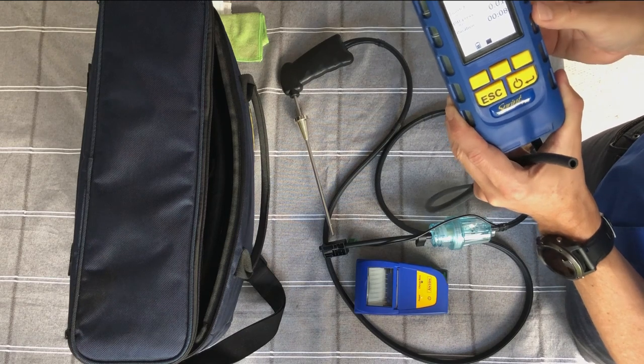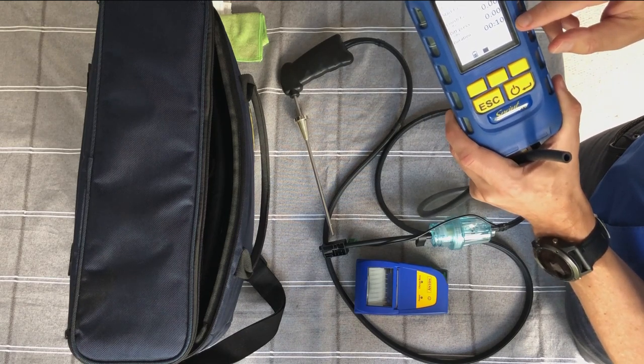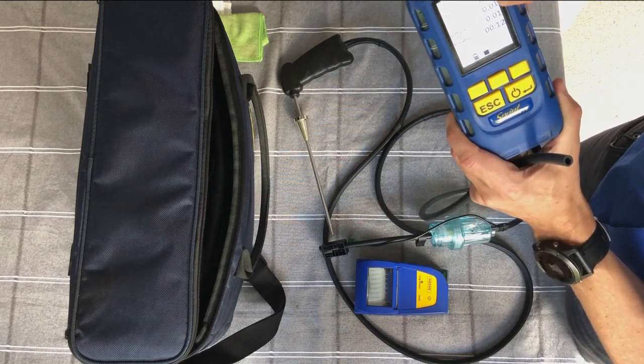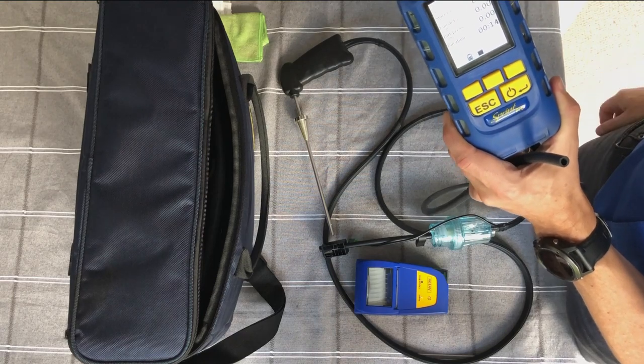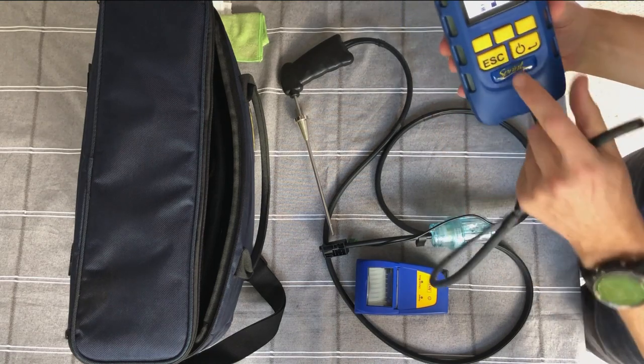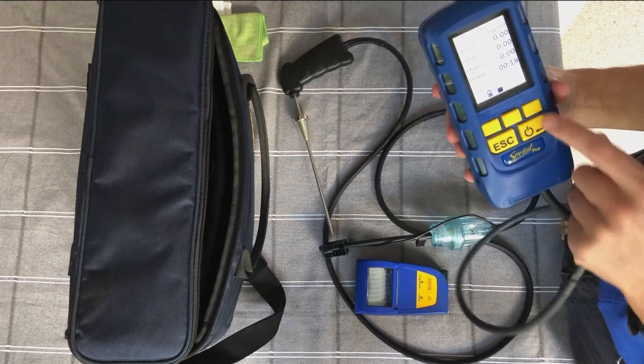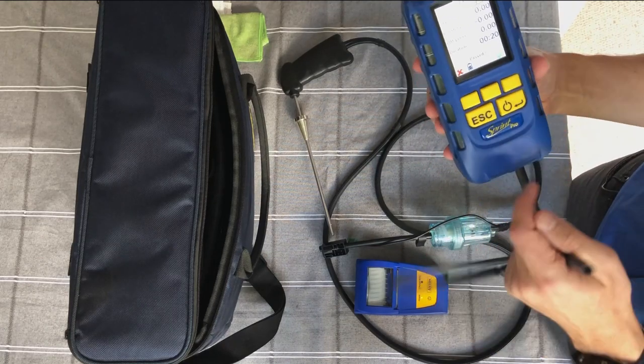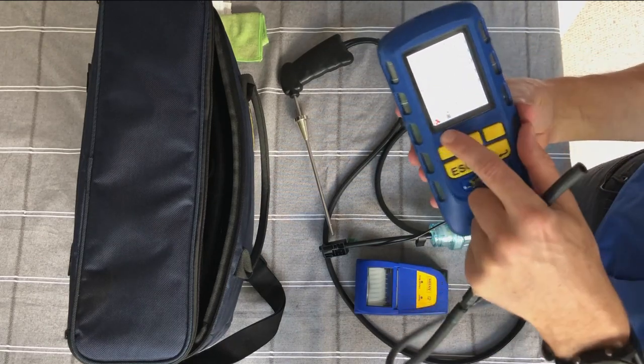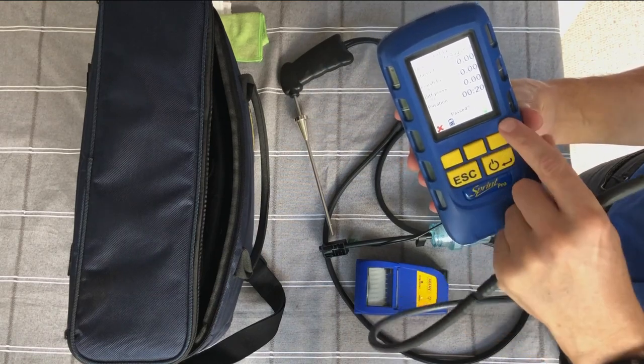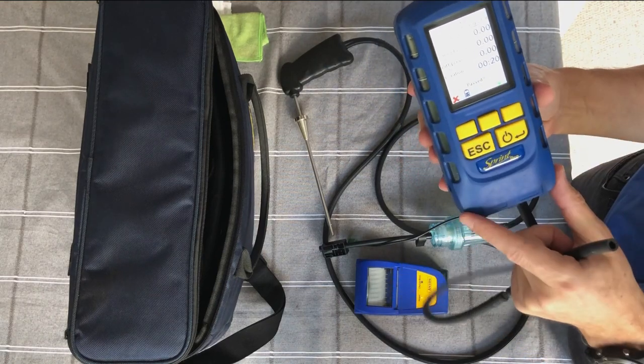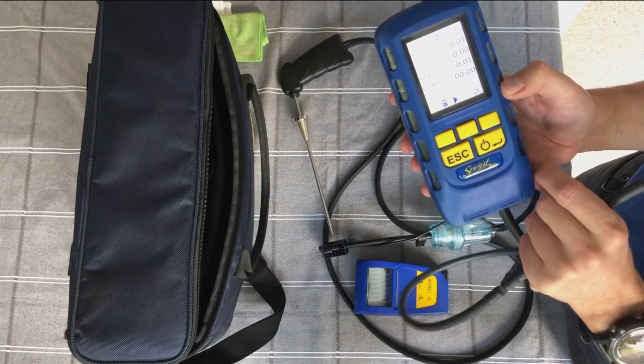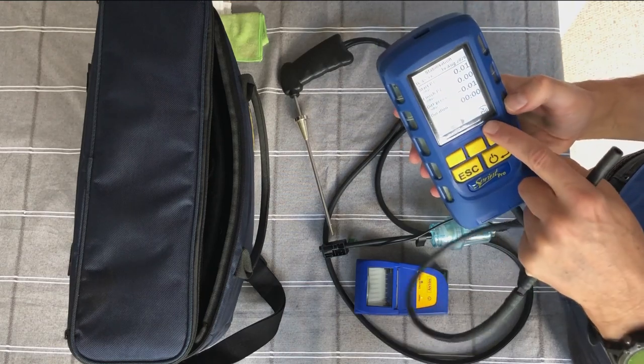When you get to the minute, or whatever time you're testing it for, you've got your start pressure and your finish pressure, and it'll show the differential, the difference between the two. So at the end of that minute you'll stop it and look at the readings. I've obviously stopped it a bit early. Pass or fail, these buttons relate. If you're happy with the readings and say yeah, that's passed its let-by test, you can press the green tick.